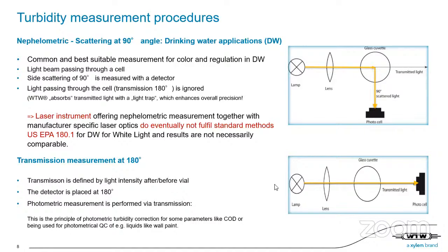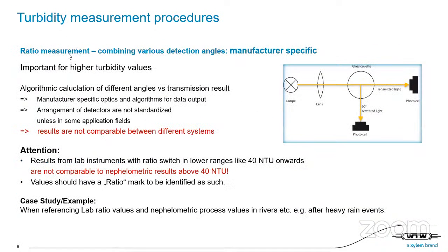Transmission, you know very well, because this is done in a photometer as well. So I have a lamp, and the lens is just an optical precision and bundling instrument. We have the vial, and at the end, going through directly at 180 degrees, there's the photocell. By the way, this is the turbidity correction of COD, for example, in a photometer. Then we do have a ratio measurement. The name is what it says. We have different angles. This is just an example. It can be all kinds of angles, for example in breweries or other applications. This means I detect several scattering signals at different photocells. And finally I do a calculation, with an algorithm behind it, and then I do a data output.